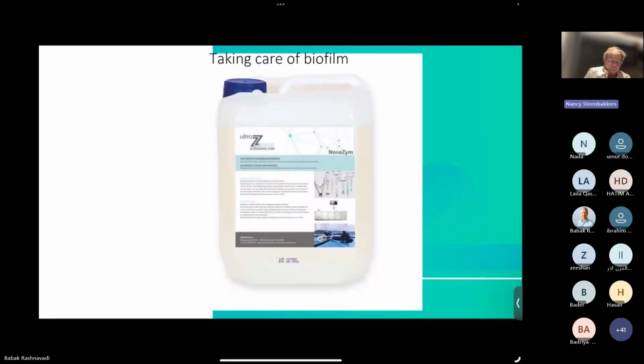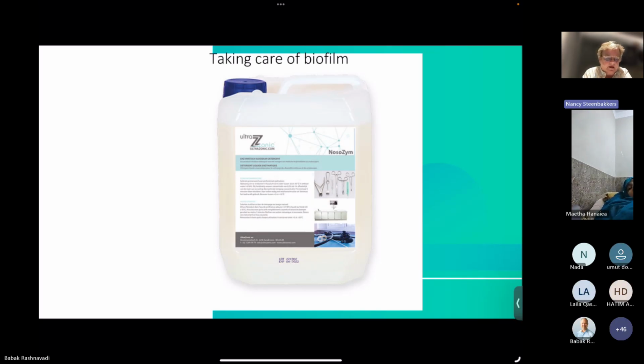Taking care of biofilm: there are some products in the market, and most of them have to be an enzymatic one, because the enzymes really destroy the biofilm, and then you can rinse it off very easily. But there is a difference between enzymes and enzymes. The enzymatic that we were creating now together with Medalcan from Greece, they made a mix that really destroys your biofilm in 3 minutes. With all other products in the market, you have to take care of 10 minutes of contact time. You have to respect those 10 full minutes, and you don't have that time. So that's why we created this 3 enzymatic detergent, where it's proven that you kill the biofilm in 3 minutes. And this is very handy when you're doing the cleaning of your endoscope. You don't waste too much time to achieve a good cleaning efficacy.